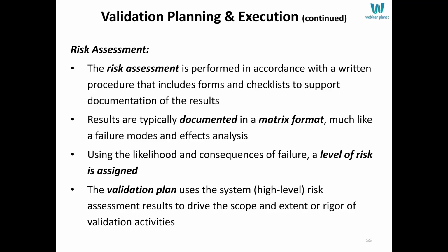The risk assessment is done in a way that, for each requirement, for example, you are looking at the potential risk of that requirement failing. What would that risk look like? If it's high, you want to do more testing. If it's low, you do less testing. You document the results in a matrix form, and you use things like the probability or likelihood of something happening, the consequences, the severity of failure, the detectability, would you know it happened, and whatever procedural and technical controls you have in place to mitigate risk, and weigh those 4 factors together. In the validation plan, you're going to have that high-level risk assessment for the overall system.